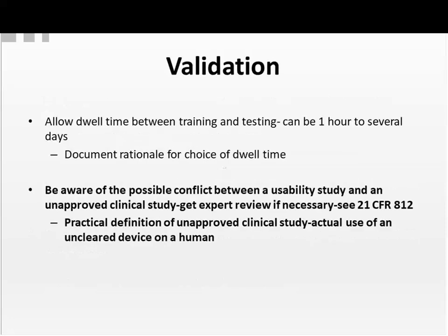Here's a very important point that must be adhered to. The FDA has rejected many validation studies because people did not address this. You must allow a dwell time between the training and testing. If you're giving the participants training, if training is going to be part of your offering, you must allow a dwell time between the time of training and the time of testing.